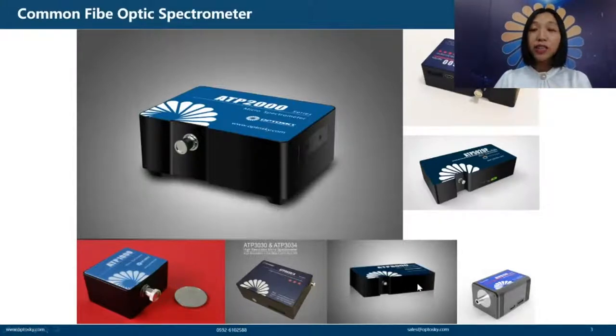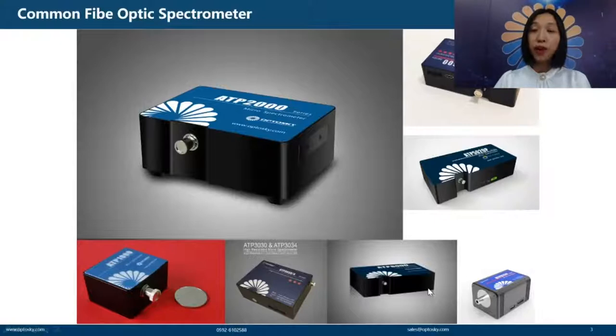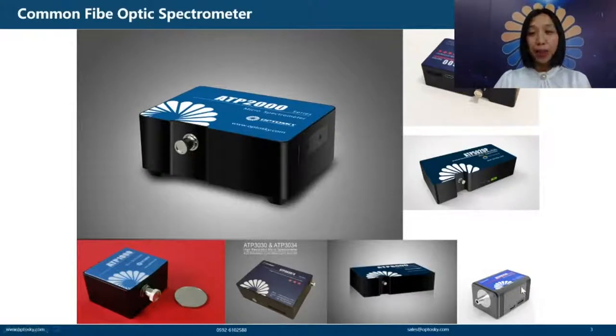We also have longer spectrometers. It's longer because it's designed to be installed inside an enclosure and has reserved ventilation ports for heat dissipation, as these are cooled spectrometers. And this is the mid-IR spectrometer.